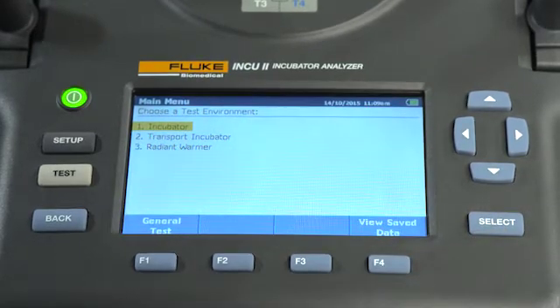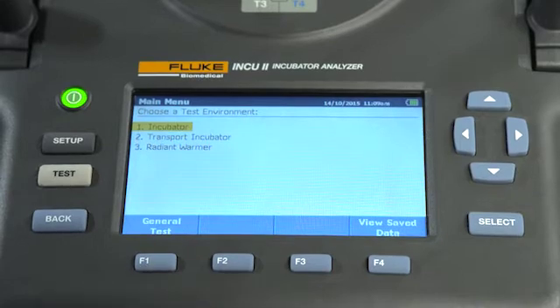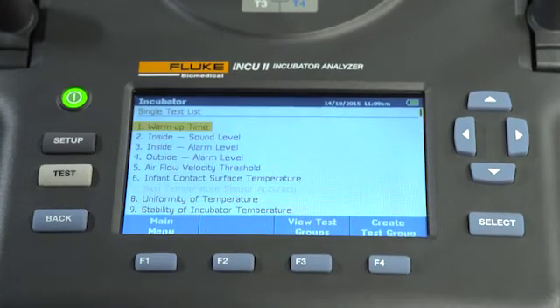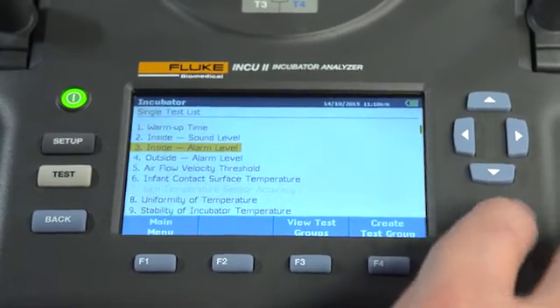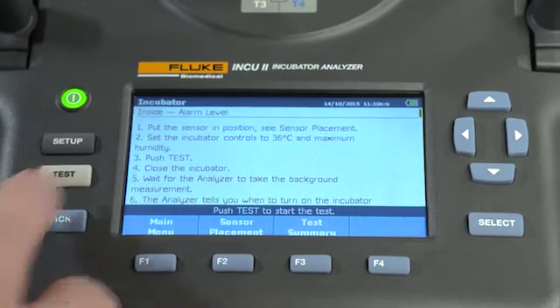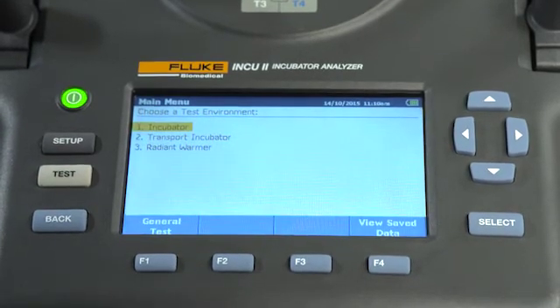You can also choose the general testing option, which allows the user to log data without testing to a specific standard. But in this example, we're going to test to a standard. Let's choose the IEC standard we want to test against. Follow the on-screen directions, then press test. The INCU II displays test results in real time. At the end of a test, either pass or fail indicators will be displayed.